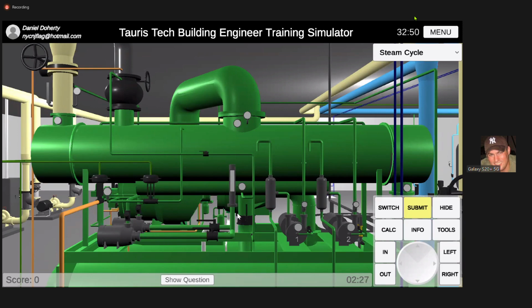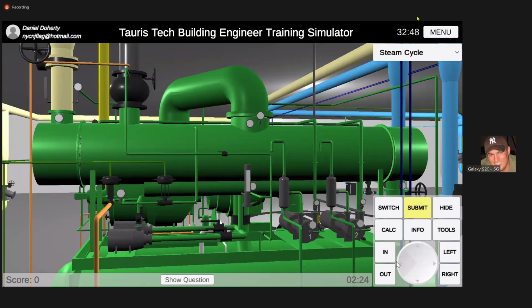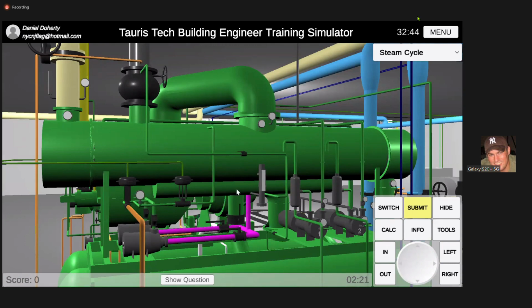Yeah. So your condensate from the hot well, it comes in right here. You see the hot well? Yeah. That's on the bottom of the hot well. Okay? These pumps pull through the pump. It comes out, this is the condensate pump header right here, suction, and this is your condensate pump discharge. Okay. And then when it discharges, it will either go this way to the recirculation valve. Got it. And dump the water back in, or this valve will close, and then instead of going that way, it goes this way, and the overboard valve is open. And then it dumps back to the boiler as makeup water to the boiler.